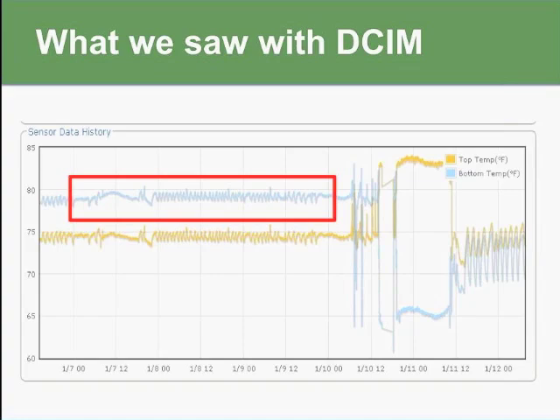And the first thing we saw was that one of our crack units, the supply air, was actually hotter than the return air. So you can imagine that when we discovered that, we were just scratching our heads thinking, what a waste that was to have that CRAC unit running for so long. And you can see on January 10th is when we turned on the Vigilent system, and immediately the supply air temperature dropped well below the return air temperature. And going back to my comment earlier about maximizing the delta between the supply air temperature and the return air temperature, that maximizes the cooling efficiency of the CRAC unit and also the energy efficiency of the CRAC unit. So you can see that it had immediate benefits, and it was certainly a surprise to us how poorly that one CRAC unit was doing and potentially doing damage to the whole operation.